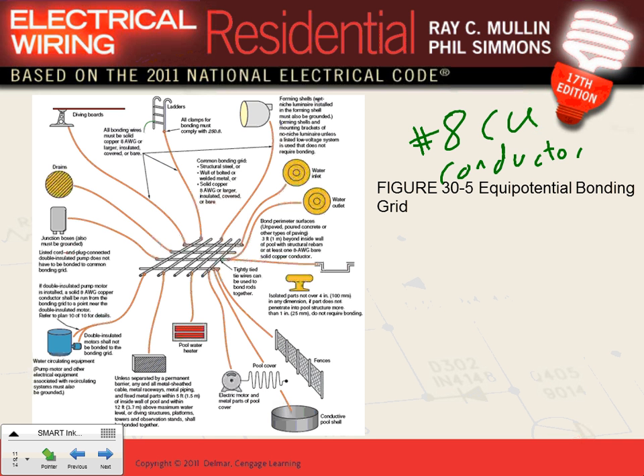Because remember, the fence is not carrying current, right? So if the fence gets energized, the circuit breaker might not trip until somebody comes and grabs this fence and touches the water, and now you get electrocuted. That's why they want to bond the fence, right? All these objects must be bonded with number 8.